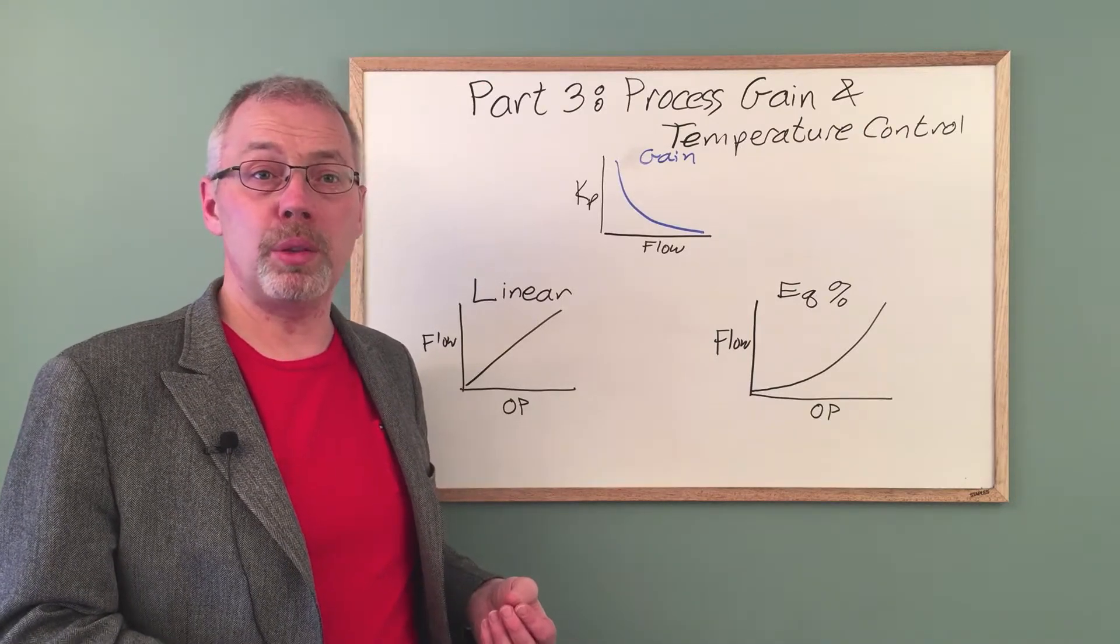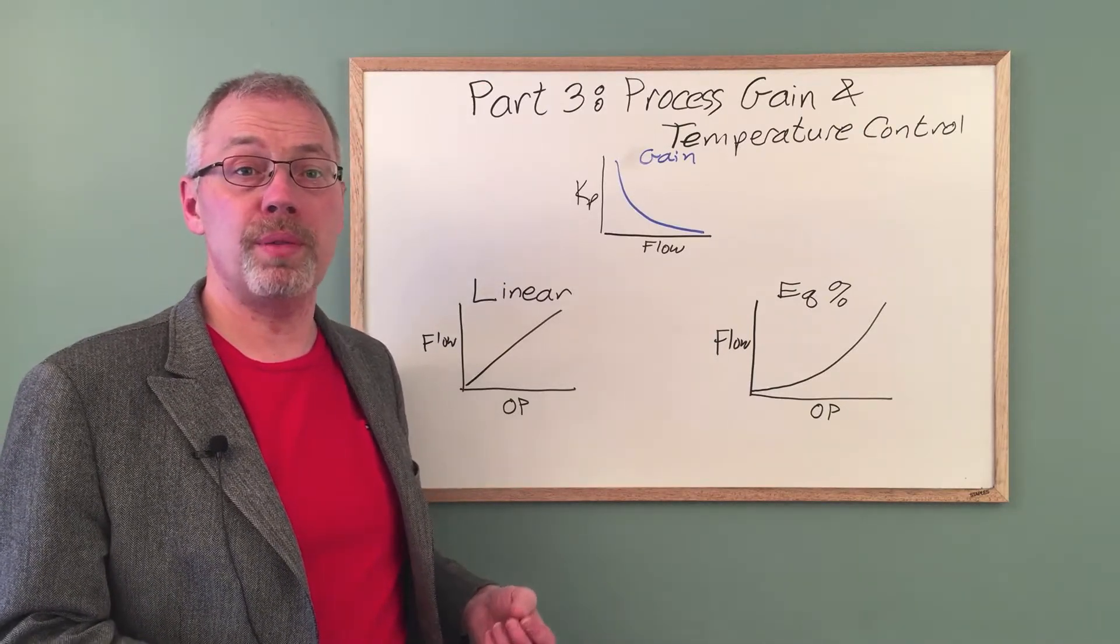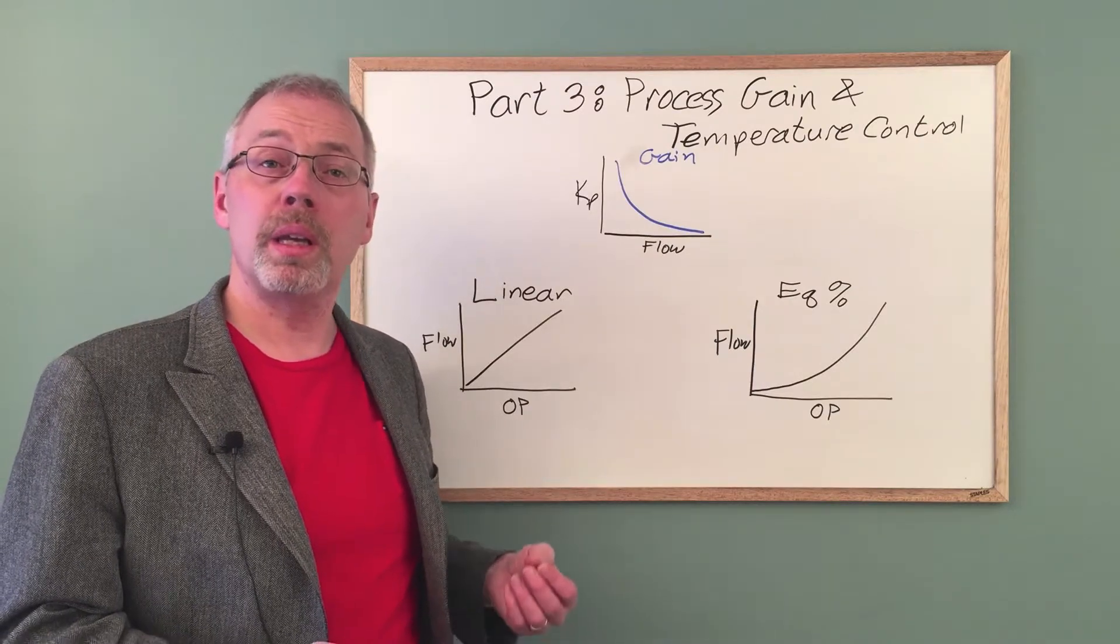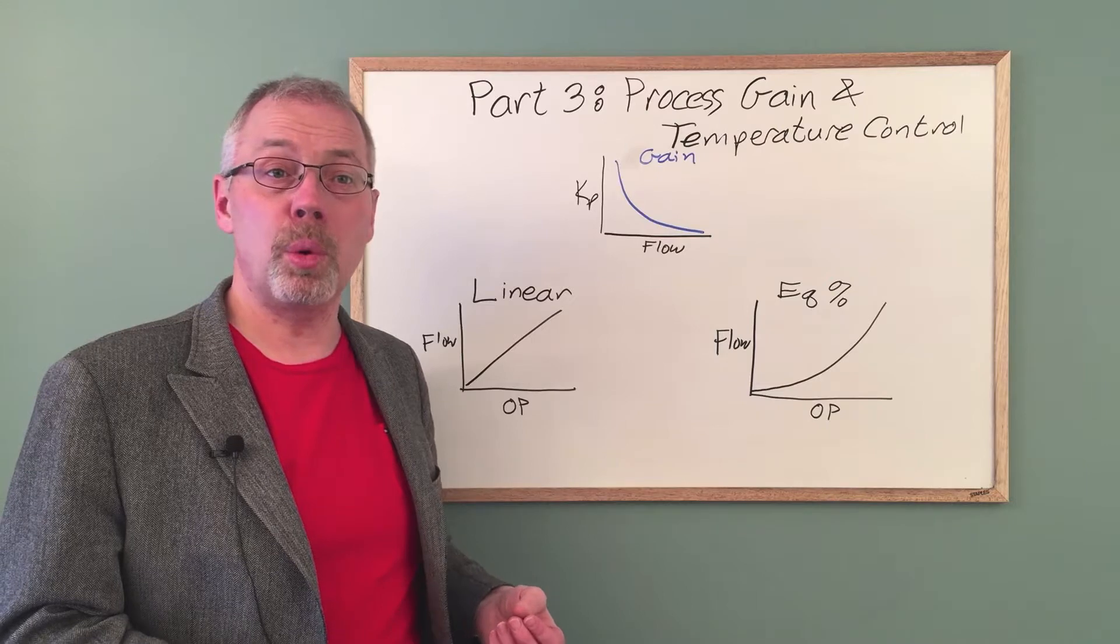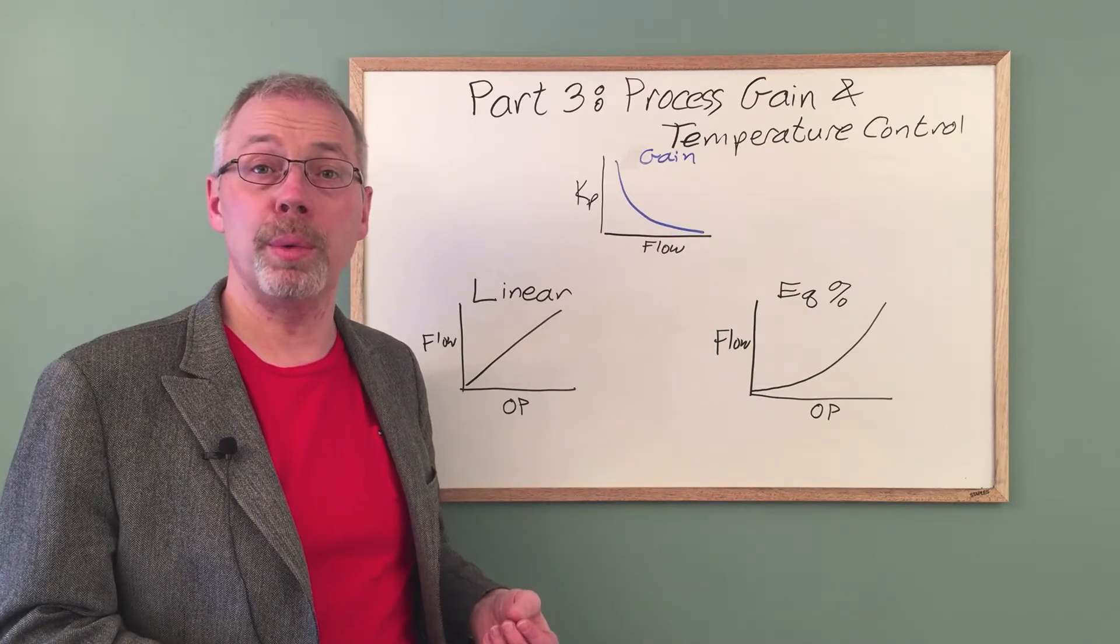But if an equal percent valve is used, the delicate action of the valve when nearly closed counteracts the aggressive process behavior. This produces a more uniform gain over a wide range of flow rates.